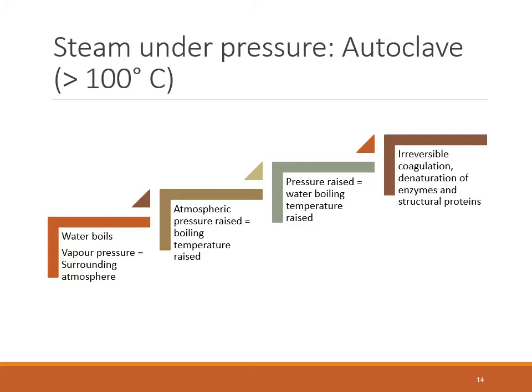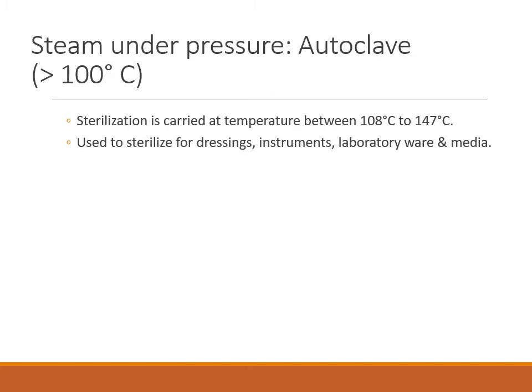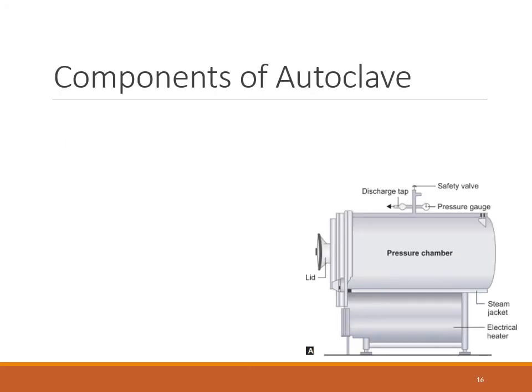This latent heat is very lethal and can destroy microorganisms through irreversible coagulation and denaturation of enzymes and structural proteins. Sterilization is carried out at temperatures between 108 degrees Celsius and 147 degrees Celsius. It is used for sterilization of dressing material, instruments, laboratory wares, and media. Aqueous solutions can be sterilized between 108 and 126 degrees Celsius.